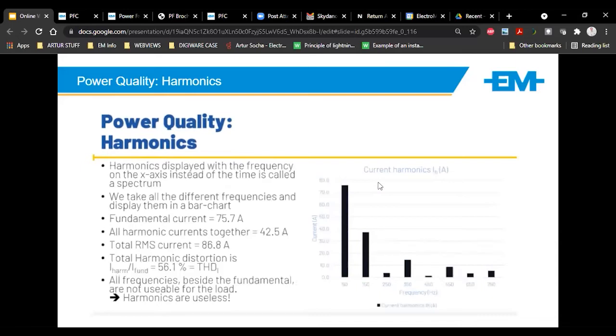So in this example, the fundamental at 50 hertz was 75 amps. But because of all the other harmonics that were measured, the total RMS, which includes harmonics, was 86 amps. So you see it actually increased the current which would have been there. And that's not useful. All frequencies beside the 50 hertz are not useful. You're just going to be charged extra current usage for that. And this is what we refer to as the current harmonic.